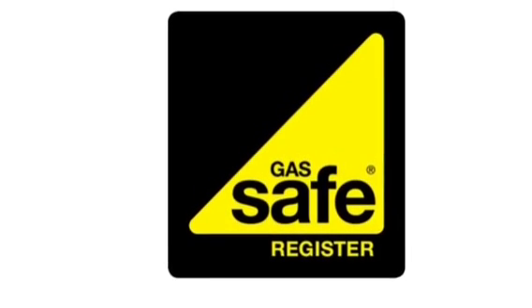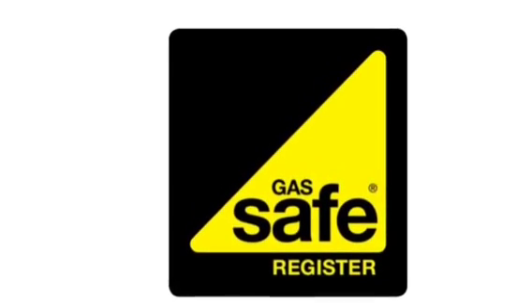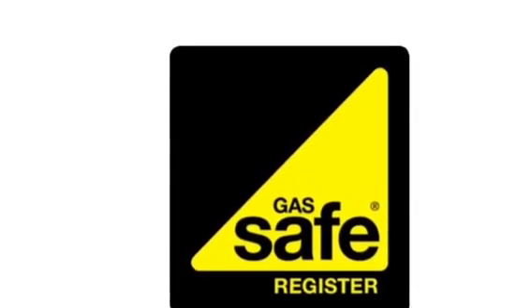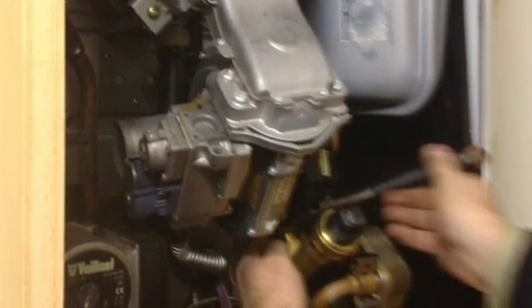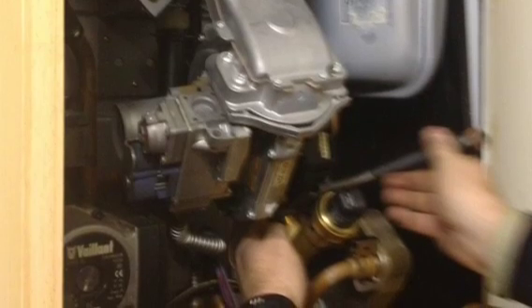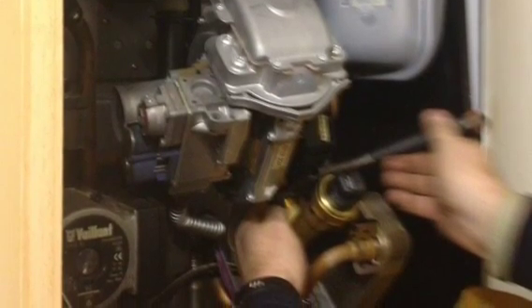On removing the cover, we diagnosed the problem was the diverter valve. While the front cover was off, we noticed that the main heat exchanger was showing signs of distress. It was damaged and was spilling carbon monoxide into the kitchen.